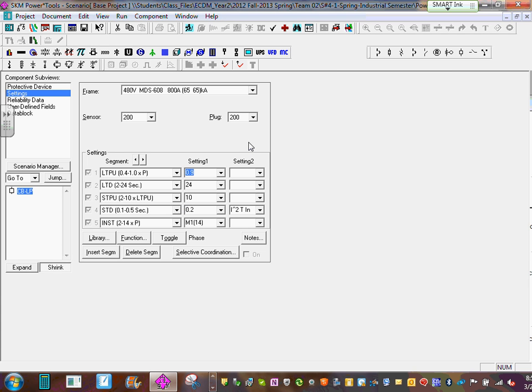Now that is a 75. Now what's 0.9 of 200? 180. So I set it up at 180. It's good enough. The cables will have enough juice for them. Do you guys see what I did? Can you give me a thumbs up, Chad? We know how to go to every one of these circuit breakers and adjust accordingly, right? All the circuit breakers that we did.